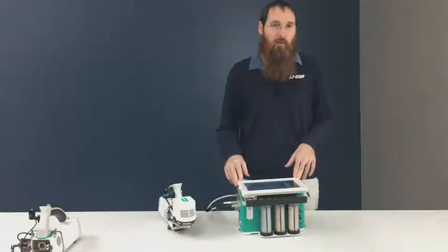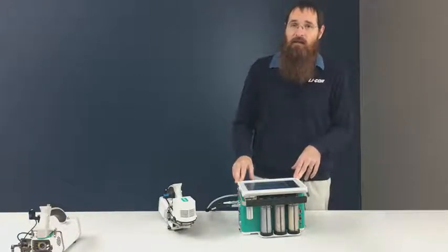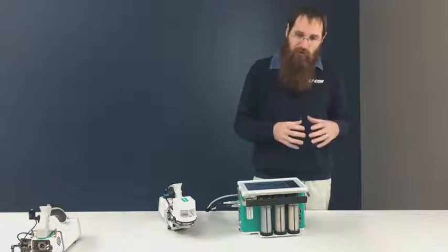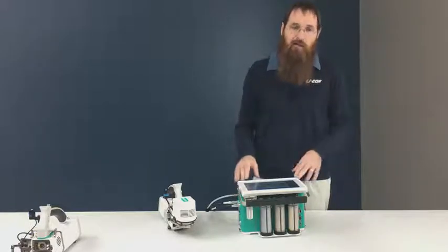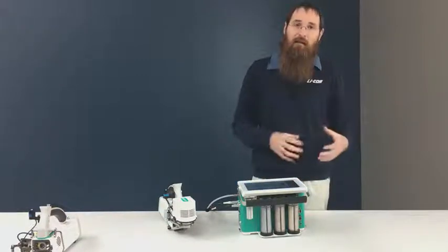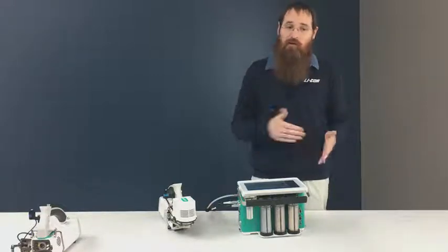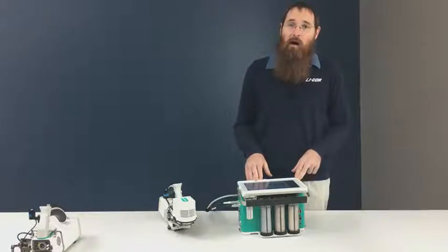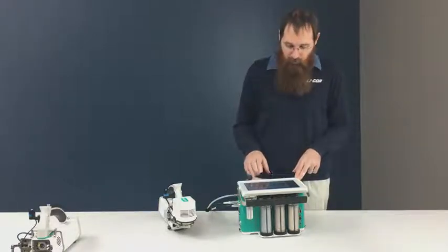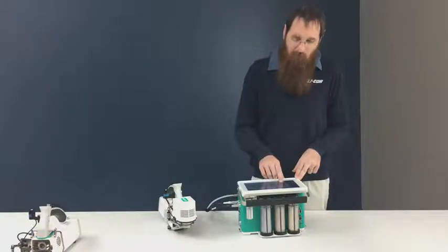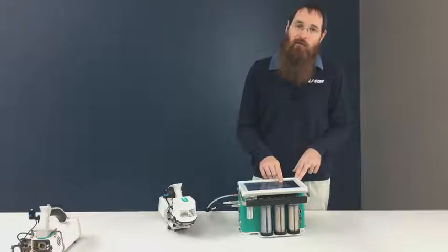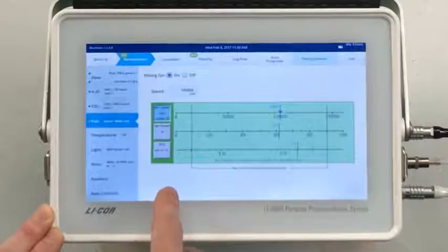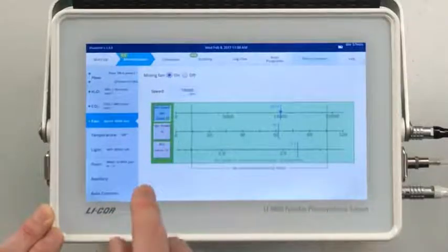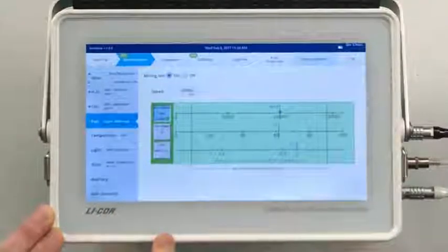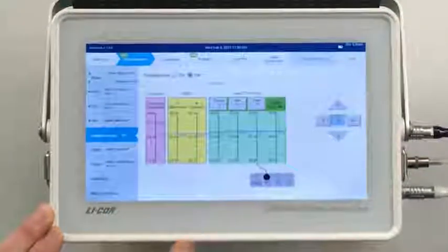So this has some consequences for the way we do things like boundary layer conductance on the instrument. In a 6400, we would take that arbitrary fan speed and leaf area, and we would go to something that's more or less a lookup table, and we would come up with what your boundary layer conductance is. On a 6800, we use fan speed, leaf area, chamber geometry, in some cases the orientation of the leaf inside the chamber, and we model boundary layer conductance on the fly. And that's why we have a control option here for boundary layer conductance, right? So if I know the leaf area in my chamber before I make measurements, I can hit this, and then instead of making all my measurements at a constant fan speed, I can make all my measurements at a constant boundary layer conductance.